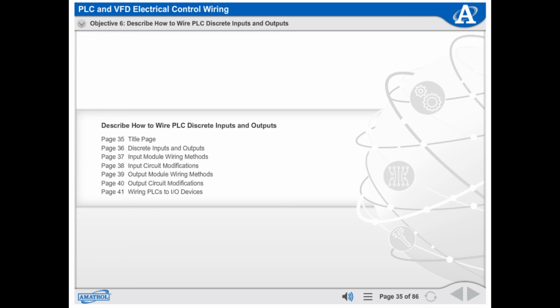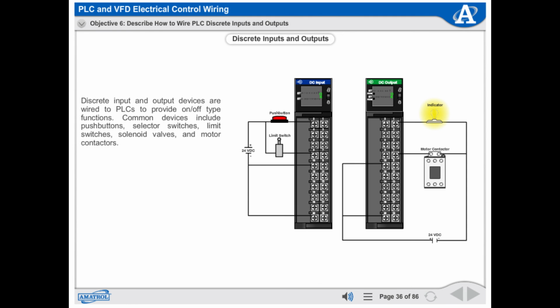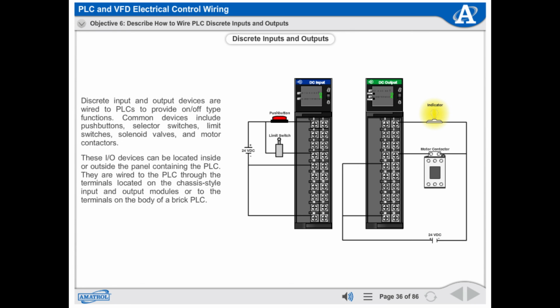Describe how to wire PLC discrete inputs and outputs. Discrete input and output devices are wired to PLCs to provide on-off type functions. Common devices include push buttons, selector switches, limit switches, solenoid valves, and motor contactors. These I/O devices can be located inside or outside the panel containing the PLC. They are wired to the PLC through the terminals located on the chassis-style input and output modules or to the terminals on the body of a brick PLC.